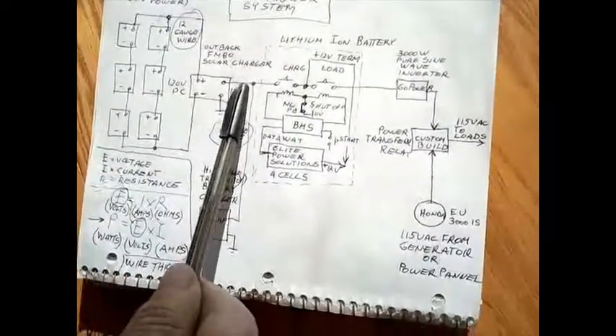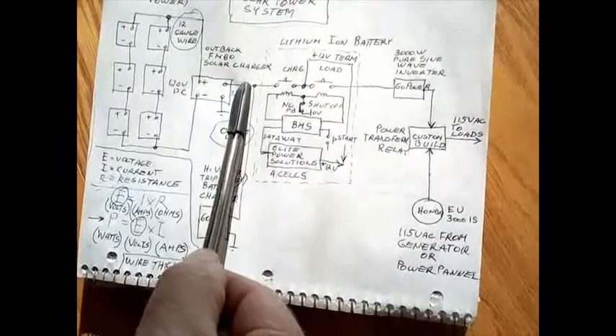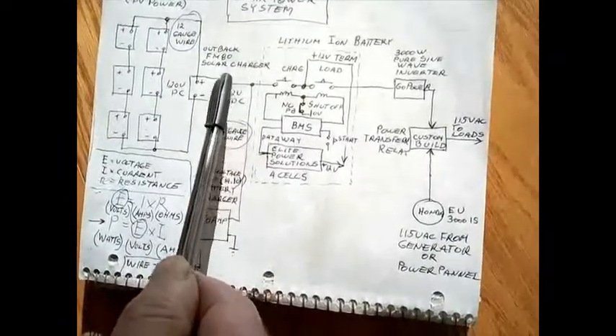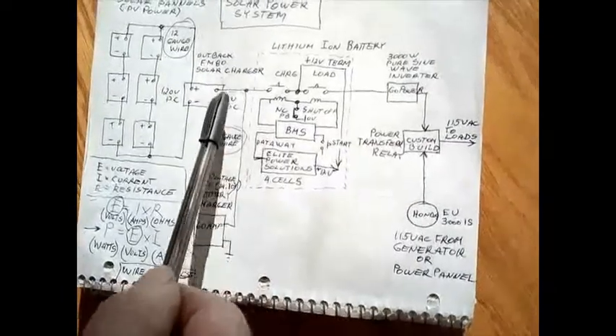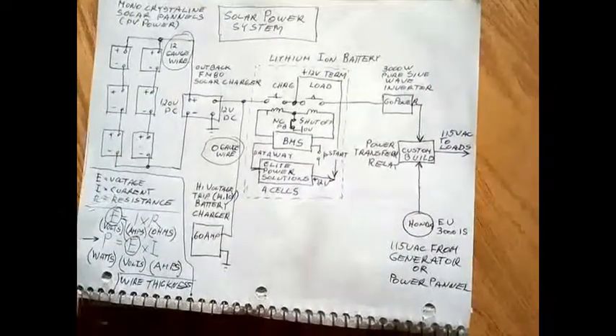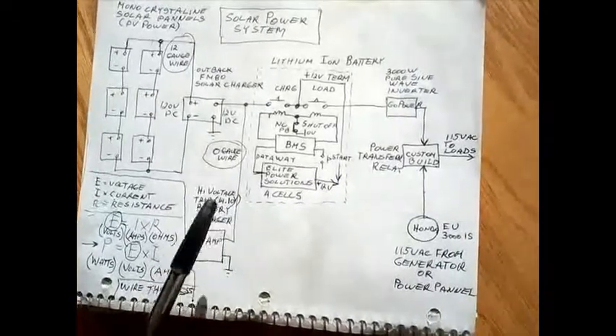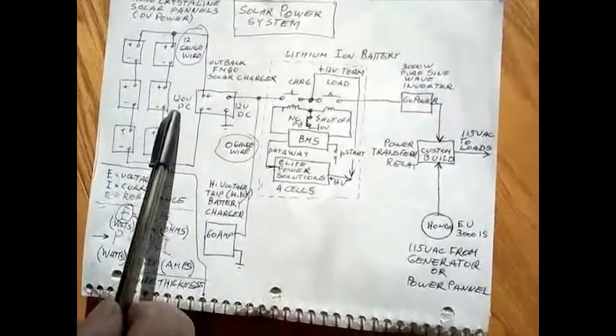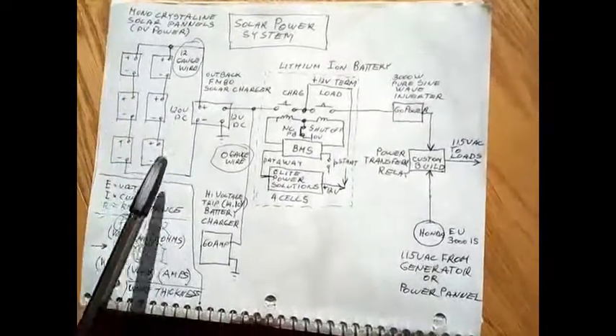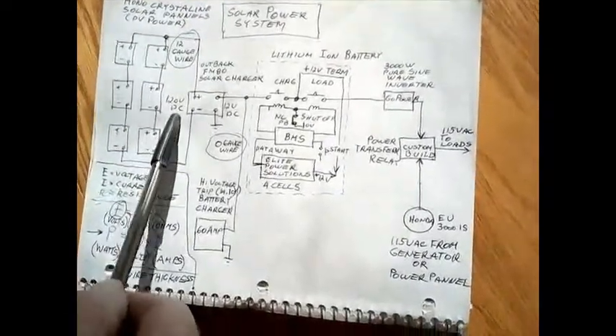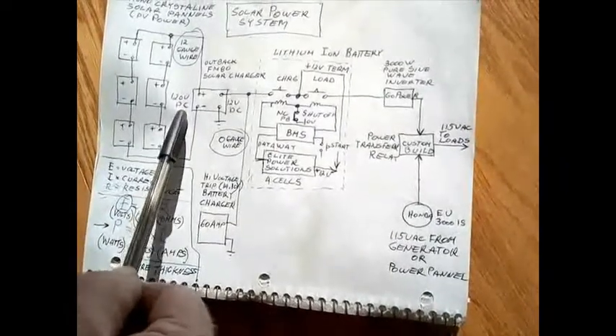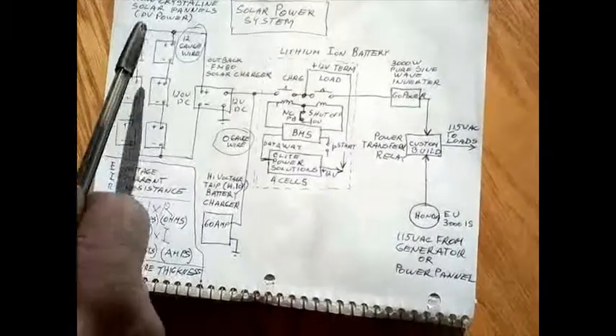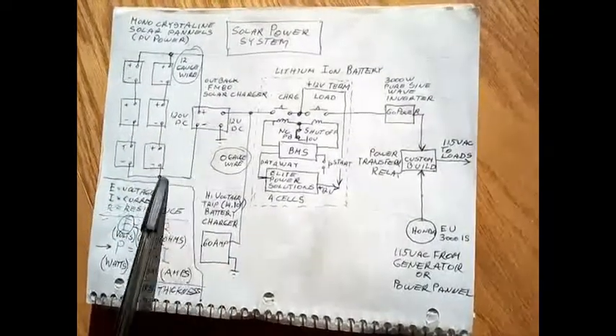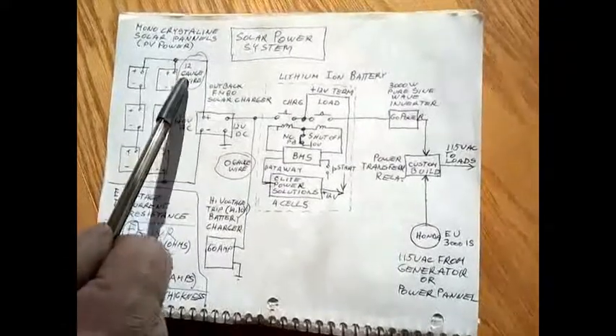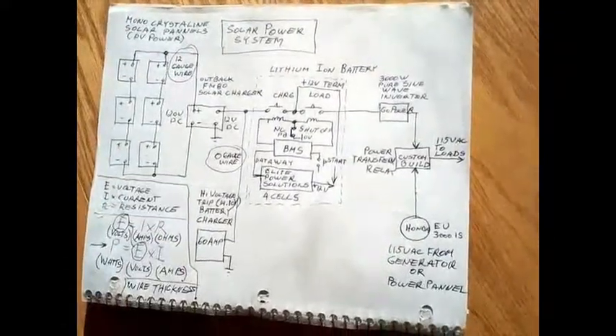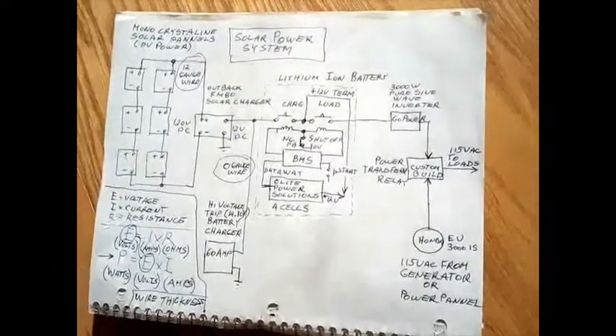When we go into heavy loads or heavy currents, we must use thick gauge wire. In this case, you're talking basically welding cable, at least a 0 gauge. When we're up to the 120 volt mark, the solar panel input side, the voltage is 10 times higher, therefore the current is 10 times less, and we can get by on thinner wire. In this case, the manufacturer of the panels has already specified 12 gauge, so that's what we use.